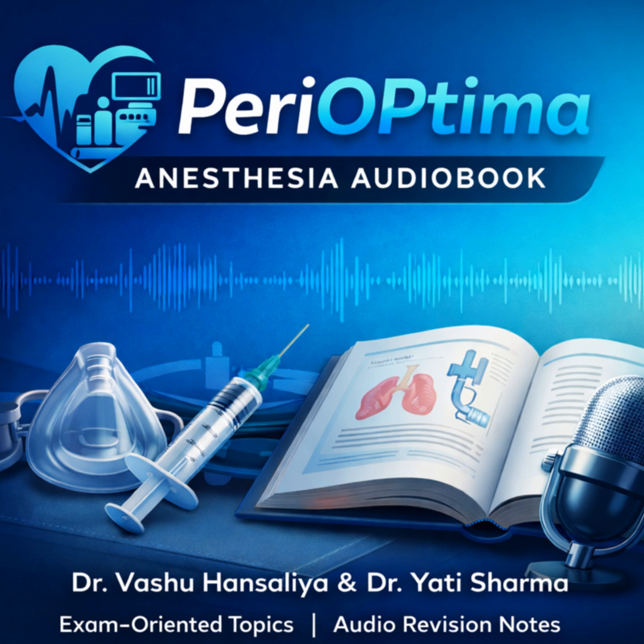Let's touch on the oxygen flush valve, the big emergency button. It is. It delivers pure oxygen at a massive flow rate, somewhere between 35 to 75 liters per minute, and it completely bypasses the flow meters and the vaporizers. So its use is for rapidly refilling the breathing bag, or, in an emergency, flushing anesthetic agents out of the circuit. But it has significant risks.